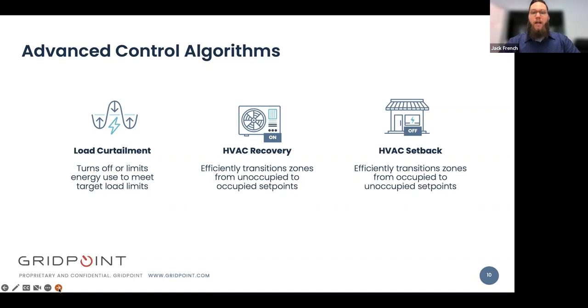HVAC recovery and setback are very similar to optimal start stop. So folks are familiar with that from maybe incentive programs that you've enrolled in, but they take it a step further because we use machine learning to figure out how long is going to be necessary for this unit to start optimally. And then with setback, very similar: how long is it going to take for this unit to drift if we turn it off right away? So we allow the units to incrementally come on and incrementally turn off, ratchet up and down.